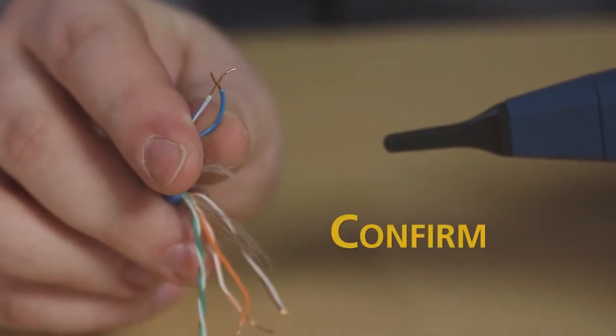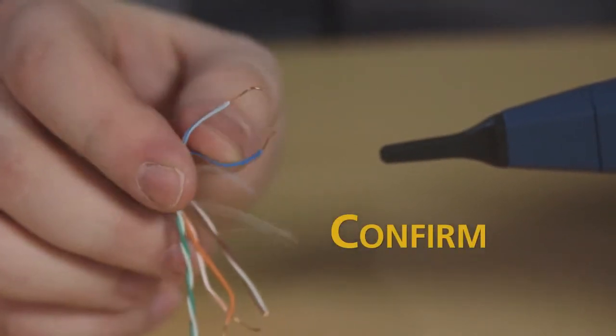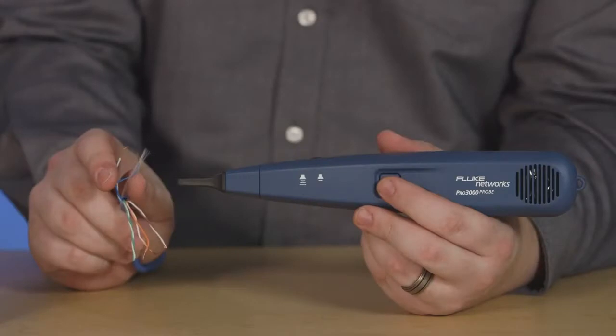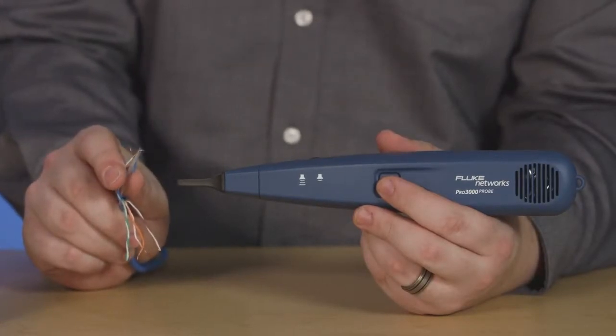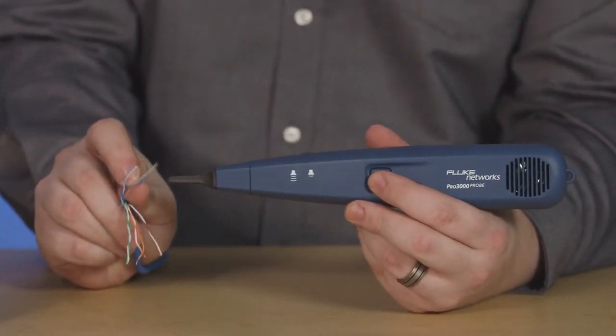To confirm you've got the right pair, simply touch the tested pair together for two seconds to create a short. If it's the right pair, the tone will change each time you short the pair.